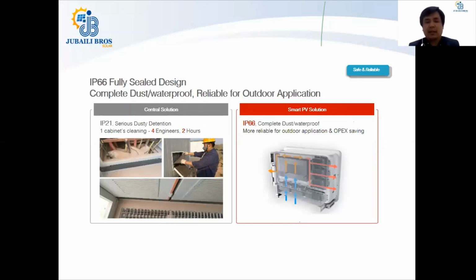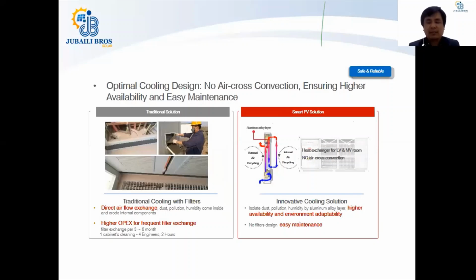Compared to it, if you have seen in the bigger projects where central inverters are used, they are using filters, and the airflow happens inside the inverter, and thus dust accumulation happens and requires regular O&M, which also results in higher failure rates if you are not doing proper O&M. So with the innovative cooling solution that Huawei provides, you get higher availability due to the low failure rate, as I said. The airflow doesn't go into the electronics compartment inside the inverter. It flows from the backside, cools the heatsink of the inverter, which is connected to the electronics part of the inverter, and keeps it cool.